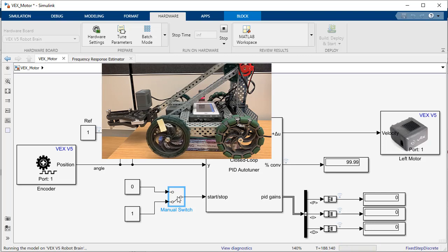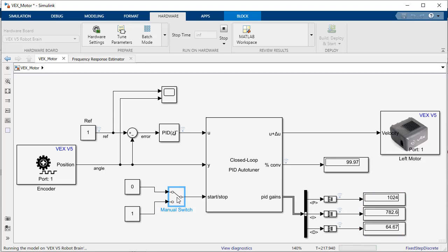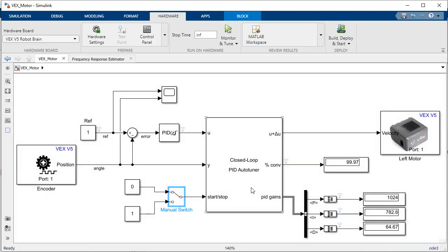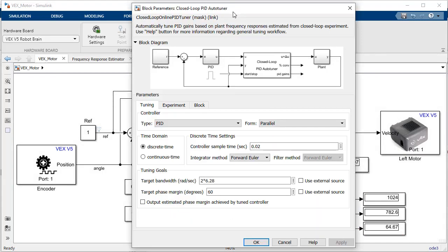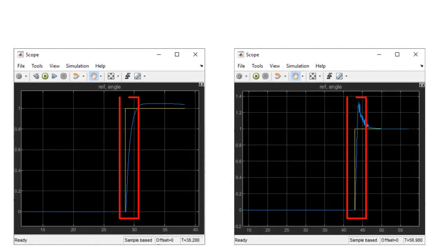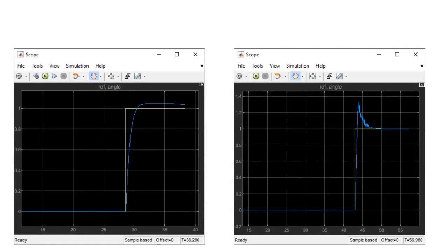After the test has been enabled and the convergence is close to 100%, you can stop the test and get the new PID gains. It is also possible to update the gains on your PID block directly from the block tab on the auto tuner block parameters. In this case, although we have some overshoot, we improved our response time and eliminated the steady state error.